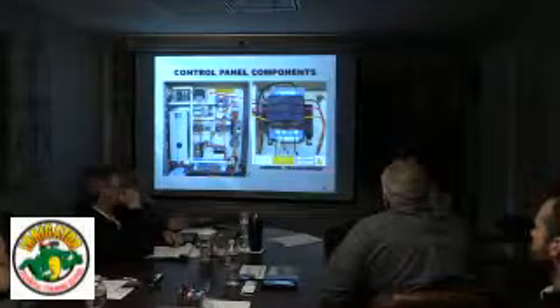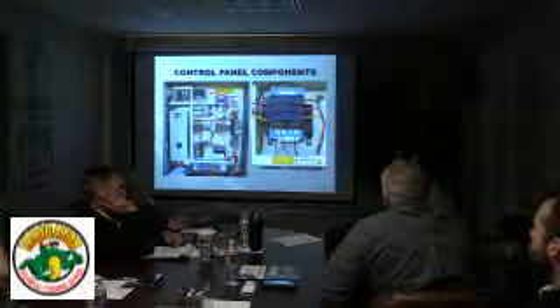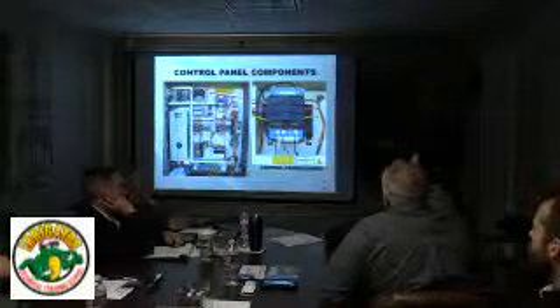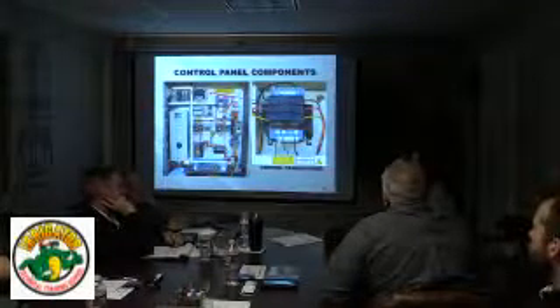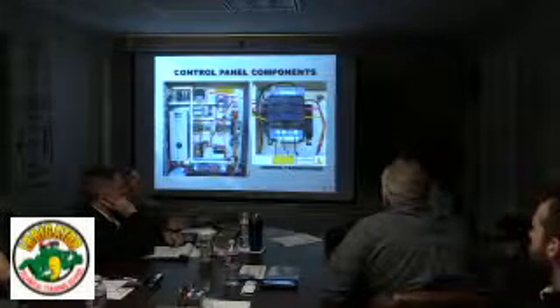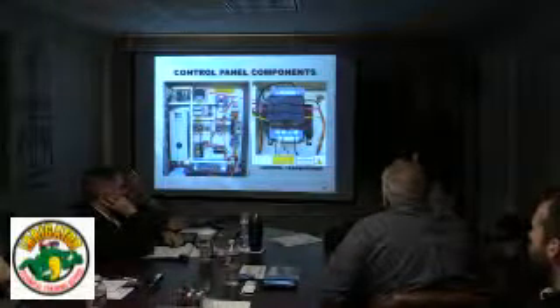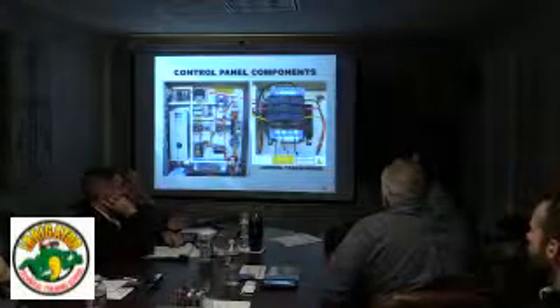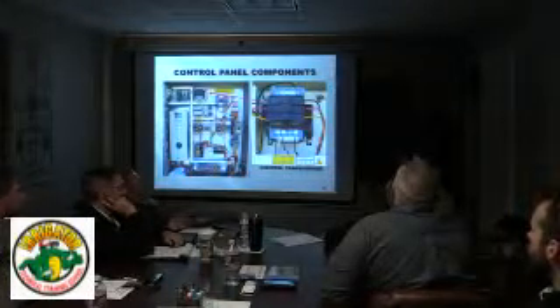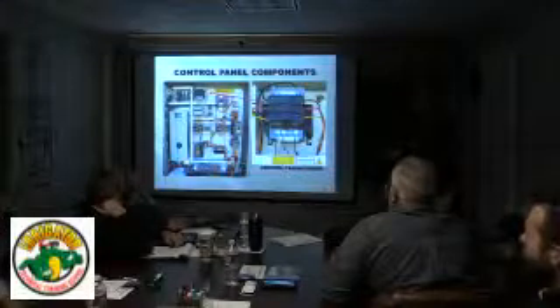Cool. Now in this case, you notice a lot of our systems, especially if they're a surface water system, may have a clear water screen out in a sump or out in the canal somewhere. We use a little 1-inch Rain Bird solenoid valve for that to turn it on only when the main pump's running. So we don't have water going out to the spray nozzles on that screen all the time, only when the main pump is running. And it's a 24 volt AC coil. So that's probably the only thing that this is used for in this system.